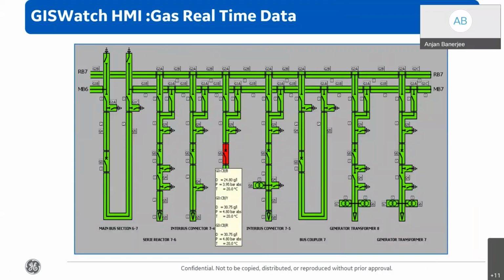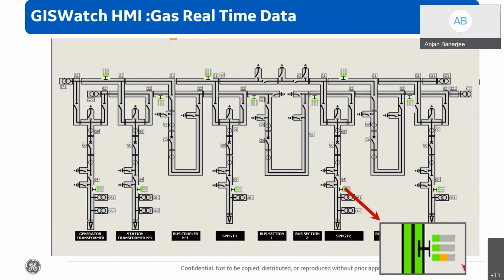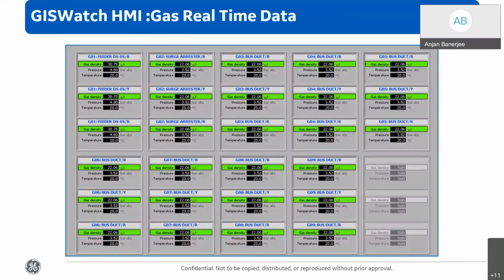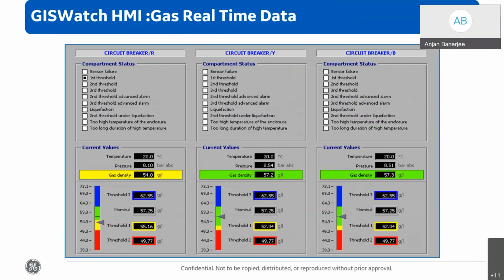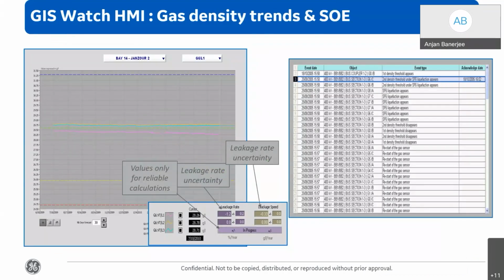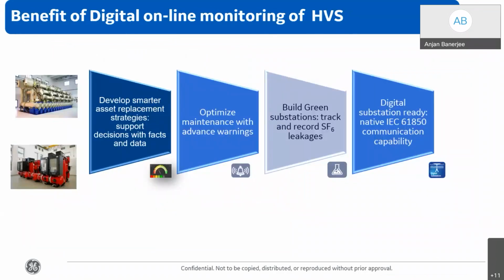Absolutely. So now over and above, we have other information like a single line diagram, which will show all the data related to gas density, pressure and temperature, as we can see over here. It will also show the severity of the situation. If the SF6 gas density is below the second level threshold, it would be indicated with a red code, and the values also will be indicated. We'll also know what the leakage rate of SF6 into the atmosphere is at any point of time. So basically, to summarize, with this kind of digital asset management, we will be able to develop a smarter asset management and replacement strategy, as all our decisions and facts will be backed up by data. We will be able to optimize maintenance with advanced warning.